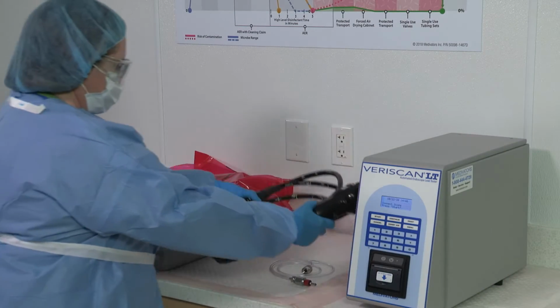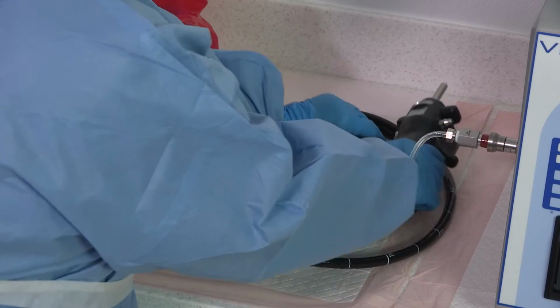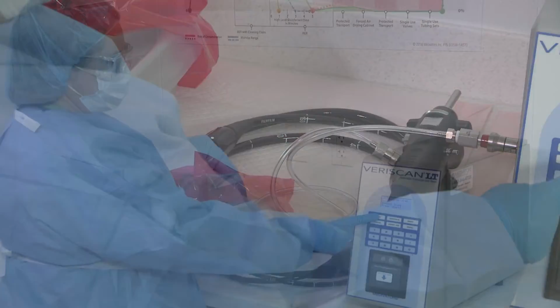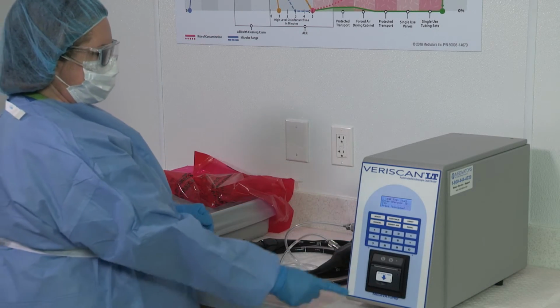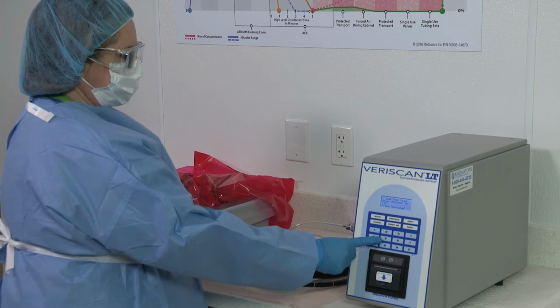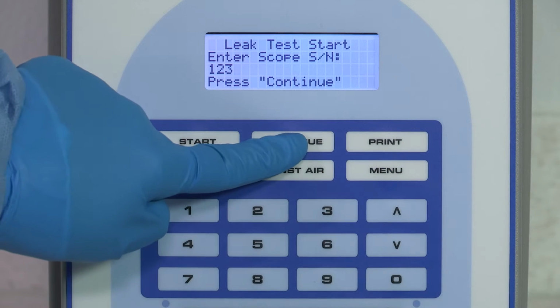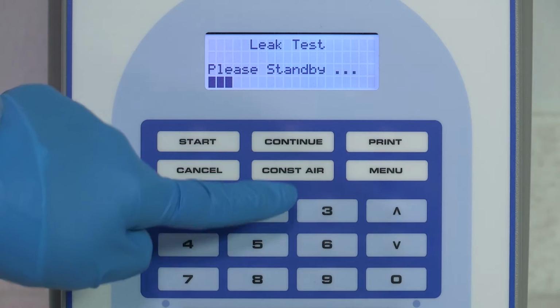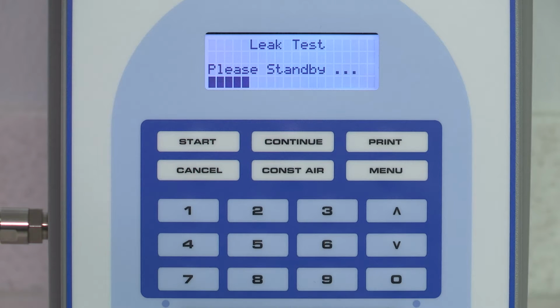The VERISCAN Leak Tester uses innovative dry endoscope leak testing technology that eliminates the need to submerge an endoscope in a water-filled sink to find a leak. The VERISCAN Leak Tester automatically detects leaks through a process of pressurizing an endoscope, monitoring the internal pressure decay over time, and electronically identifying if an endoscope leak is present.